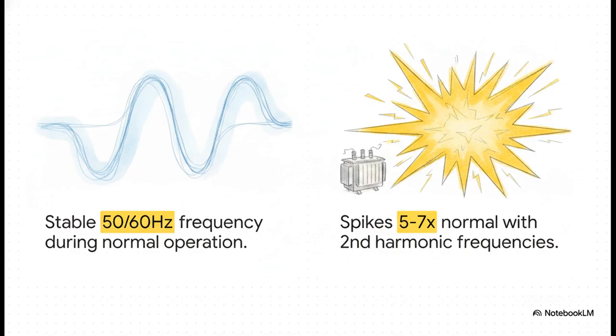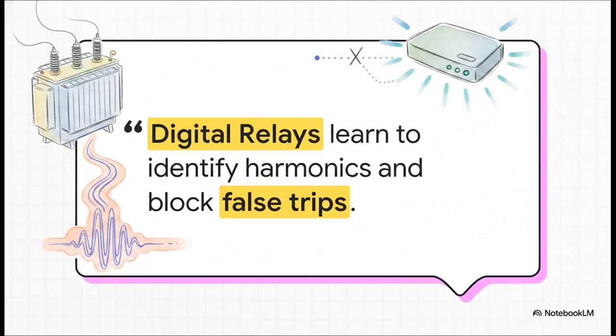To our super strict differential relay, this massive imbalance looks exactly like a catastrophic internal fault, even though it's totally normal and naturally disappears in less than a second. So how do we fix that? Well, modern engineering solved it by looking at the current's unique fingerprint.